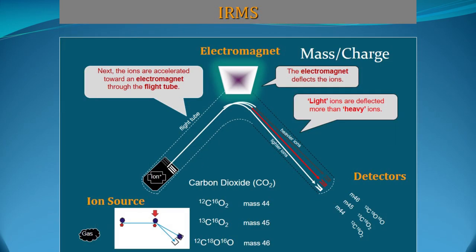There are three parts of the IRMS: first is the ion source, second is the electromagnetic field, and third is the detector. When ions enter into the magnetic field, they are deflected according to their mass-to-charge ratio. Lighter ions deflect more than heavier ions, and those ions are collected in different cups. This is the principle on which IRMS works.